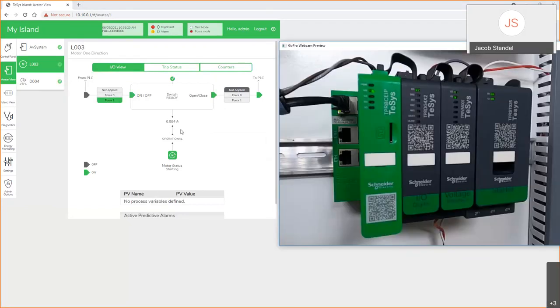We're currently pulling half an amp, and I have that configured to be an undercurrent warning. This doesn't trip the contactor, but it gives you an alarm to let you know that I might be freewheeling, or a gearbox is disconnected, or a shaft is broken, or a belt is failing. These are real situations that you run into that you'd never know about with a traditional system. Now, what happens if I increase the load? I have this motor configured for a 0.9 full load amp, and now we're hovering about 1. Now I'm getting an overcurrent alarm. Still doesn't trip, but it lets you know that you might be creeping up and there might be issues where your conveyors are overloaded, gearboxes are binding up, something's failing.